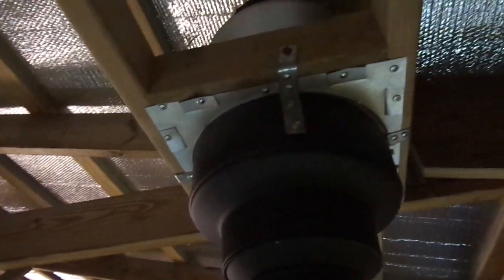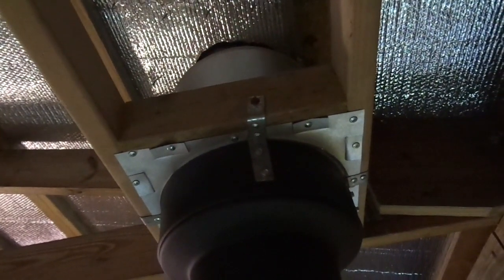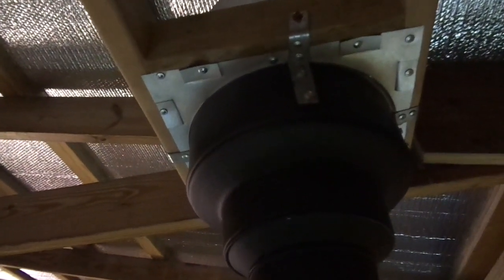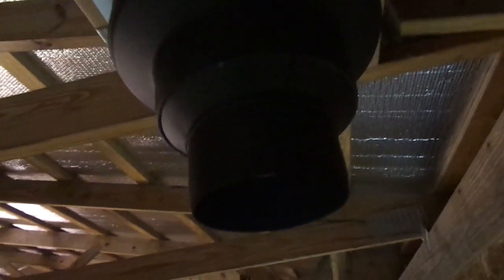This is Class A 2100 degree stainless steel fully insulated flue. It's good for a 1 hour chimney fire at 2100 degrees before it'll do any deterioration whatsoever. But you want to convert that big thick insulated pipe down to the size of flue pipe that you've got. Of course, I'm putting on the 6-inch adapter that goes from the outside dimension of the stainless steel Class A chimney down to the black pipe that's going to go down to the stove.